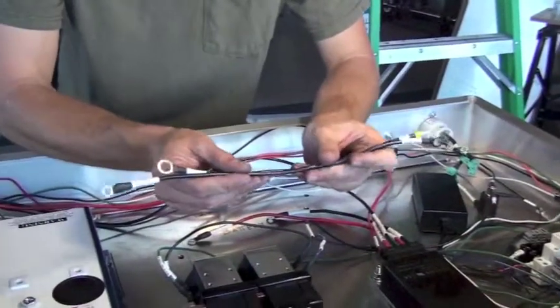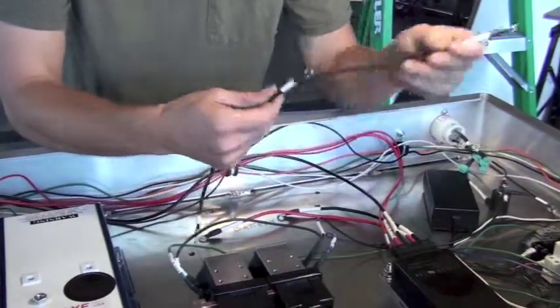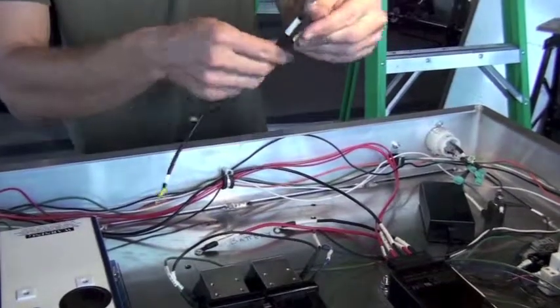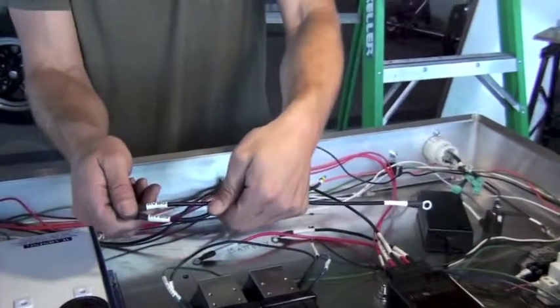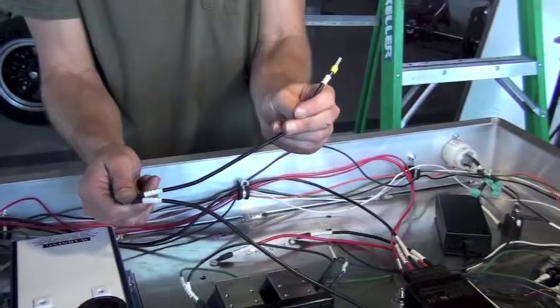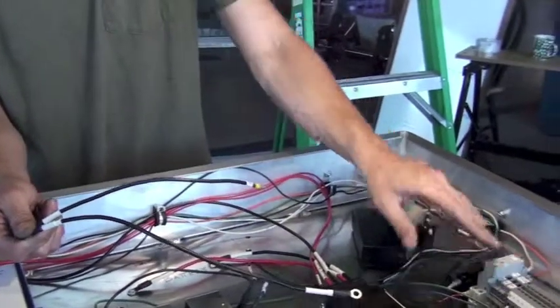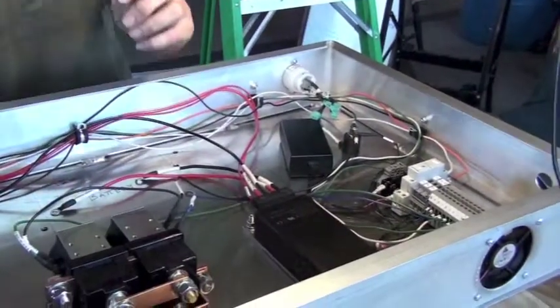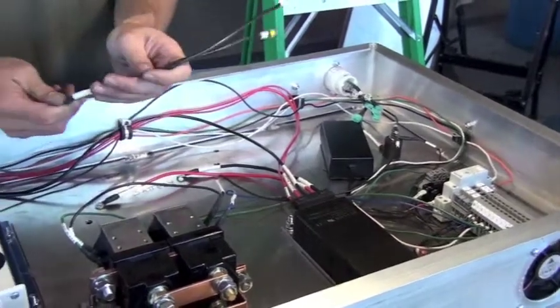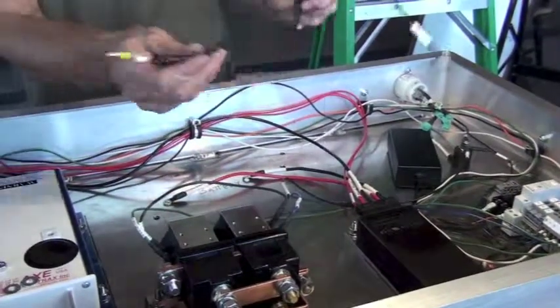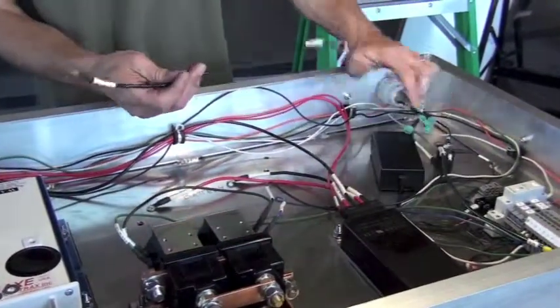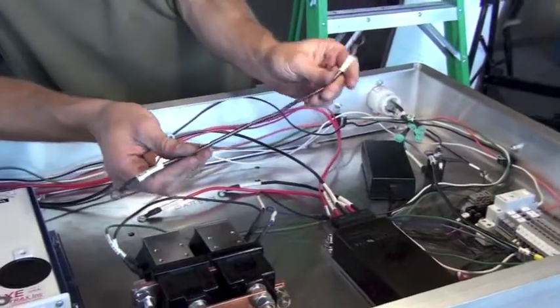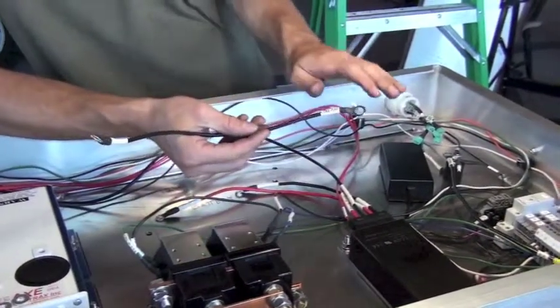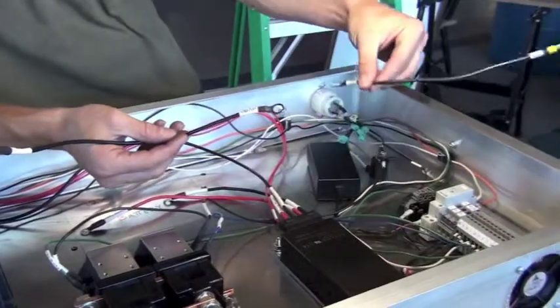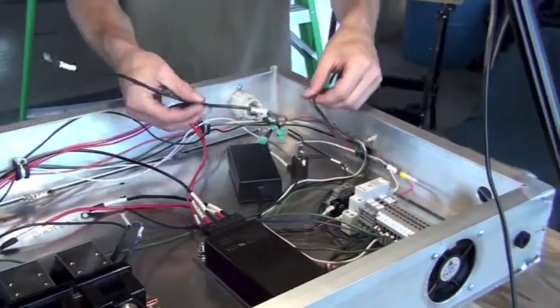Next, we're going to finish up the common ground points in our system. These two black wires go to the isolated ground in the control box. They're labeled as such. One goes to the 12-volt battery and one goes to the DIN rail. And the one that goes to the 12-volt battery has the thicker connection, the largest connection on the common ground. So we're going to put that as the first cable onto the common ground. Everything else will go on top of it.